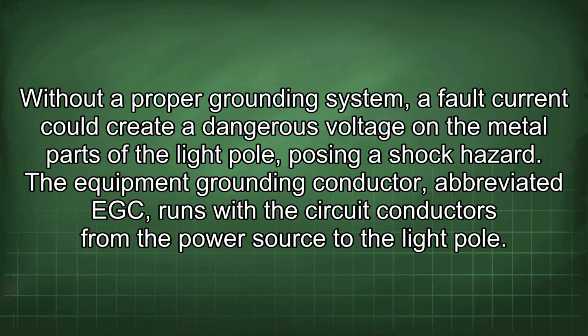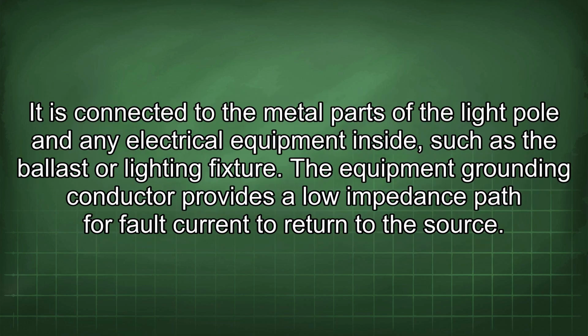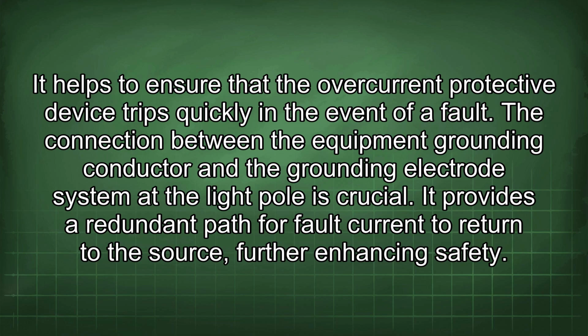Without a proper grounding system, a fault current could create a dangerous voltage in the metal parts of the light pole, posing a shock hazard. The equipment grounding conductor, abbreviated EGC, runs with the circuit conductors from the power source to the light pole. It is connected to the metal parts of the light pole and any electrical equipment inside, such as the ballast or lighting fixture. The equipment grounding conductor provides a low impedance path for fault current to return to the source. It helps to ensure that the overcurrent protective device trips quickly in the event of a fault.